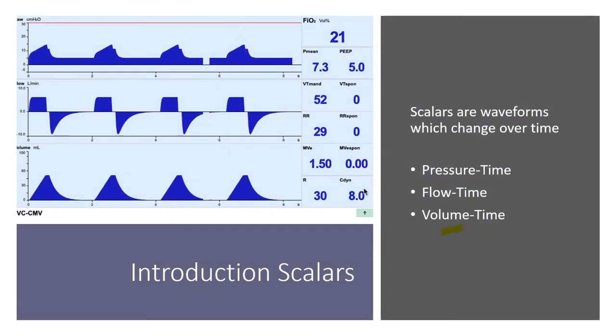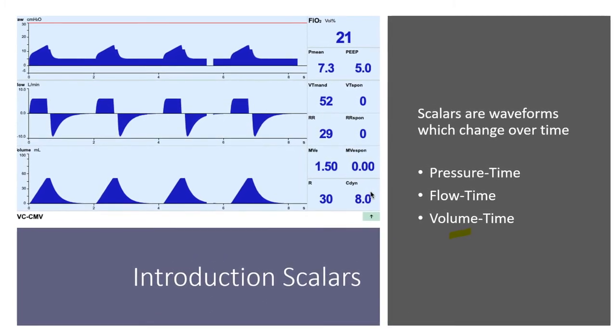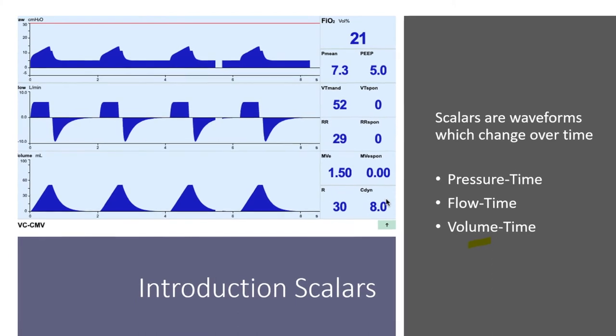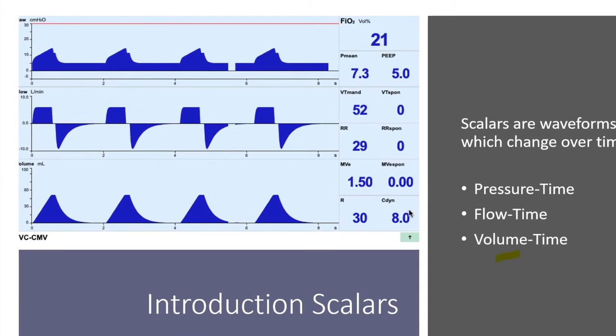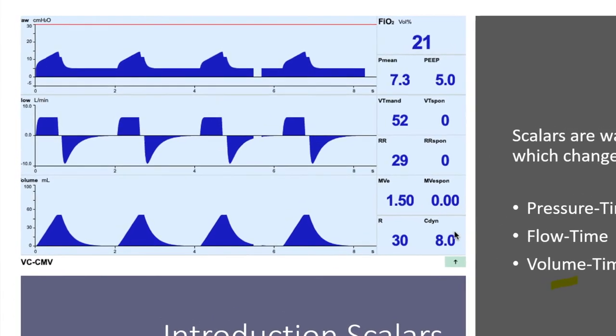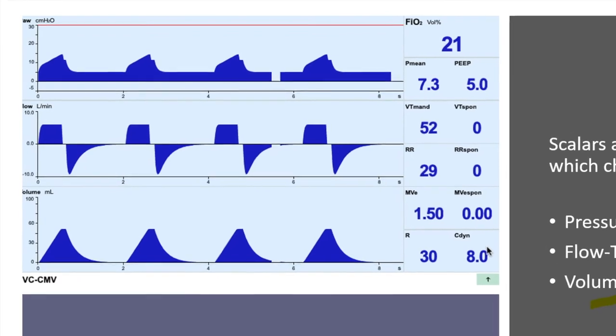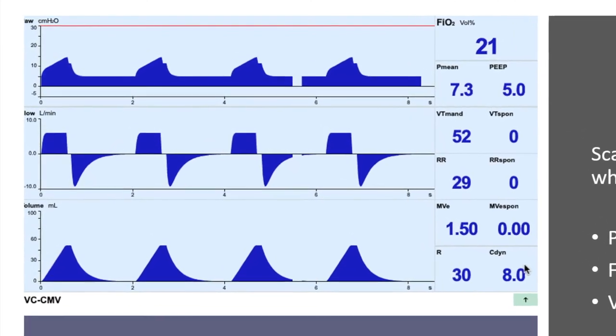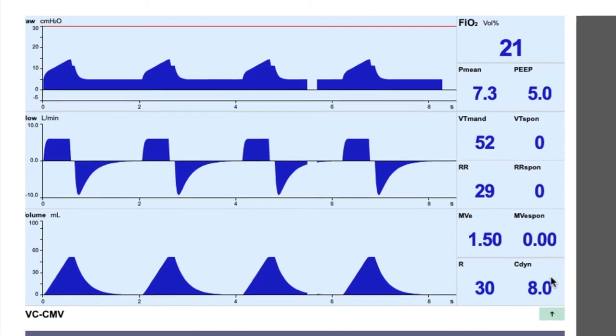Scalars are waveforms that change over time, and there are three that are very important during ventilation. At the top we have the pressure-time waveform — how does pressure vary over time. Then we have the flow-time scalar — how flow varies over time. And we have the volume-time scalar — how volume varies over time.